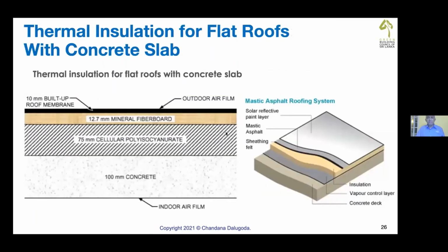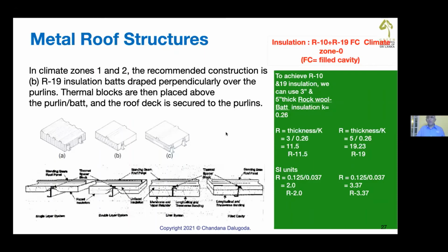Now metal roofs, you need 2 insulations, one for a cavity and one for the main insulation, fill cavity. Now we can see R values are R10 for the normal thermal insulation for the roof, and the cavity R19. So you need 3 inches and 5 inches of rock wool, about 8 inches. What we do instead, we have 2 inches thick, 50 millimeter glass wool. So remember, a normal zinc alum roof with 50 millimeter glass wool will not comply for a green building roof. You'll have to increase the roof insulation.